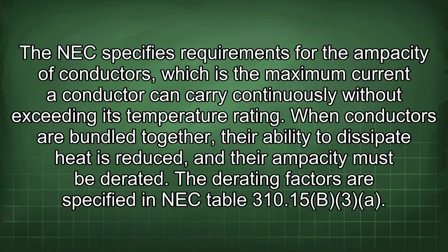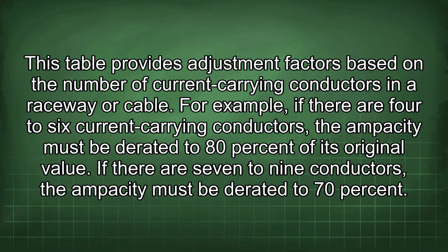The NEC specifies requirements for the ampacity of conductors, which is the maximum current a conductor can carry continuously without exceeding its temperature rating. When conductors are bundled together, their ability to dissipate heat is reduced, and their ampacity must be derated. The derating factors are specified in NEC Table 310.15(B)(3). This table provides adjustment factors based on the number of current-carrying conductors in a raceway or cable.